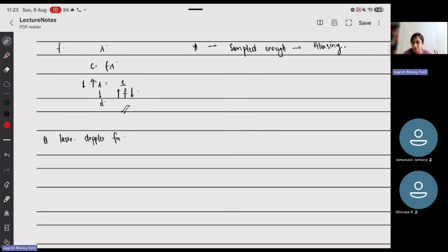Now, for laser Doppler flowmeter, it's basically what the term says. Your excitation source is now light, and what you're receiving back is also light. Light is being transmitted, and light is being scattered by your moving or shifting red blood cells. And now you're looking at the change in frequency shifts, as in how your light scatters, changes, shifts, or moves.